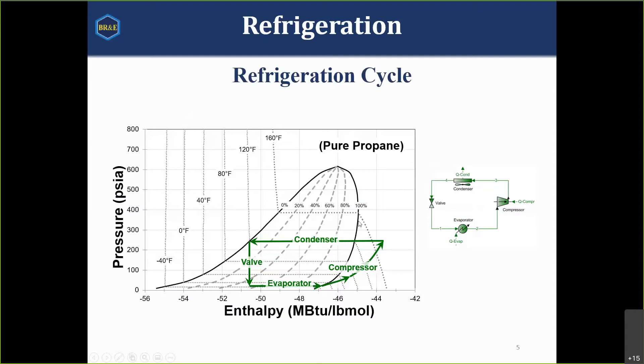This is the phase envelope for propane. On the left we have the zero-percent vapor line — the bubble point line — and on the right we have the 100-percent vapor line — the dew point line. Isotherms are plotted here, and as they come down inside the phase envelope, since this is a pure component, at constant pressure we go from all liquid to all vapor at a constant temperature. You can see the 160-degree line is parallel with a constant pressure line. If you have a mixed refrigerant you'll be crossing isotherms as you go from all liquid to all vapor at constant pressure.